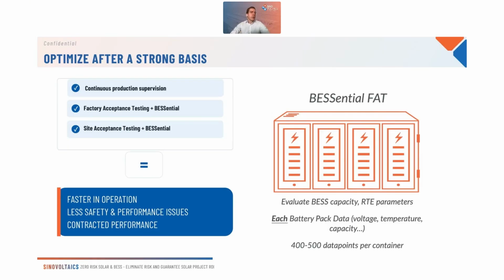Since that test is often only on the container level, but you still have subcomponents like modules and racks inside of the container, we use this BESSential software to analyze each and every one of those subcomponents during the FAT. The idea is that when we find these issues at the factory floor, it's going to be much quicker, cheaper and easier to replace and fix them than at the site, where you'd need to troubleshoot, use spare parts, or send an engineer from China to the site.